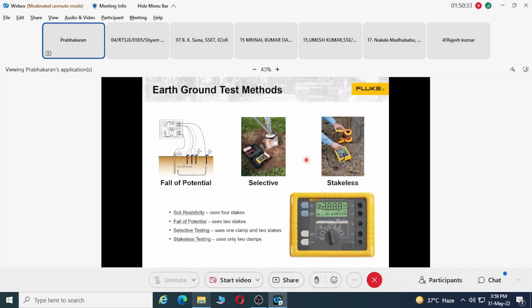Here you are using 4 stakes, and fall of potential again uses 2 stakes. You can do the same thing with two stakes also. Selective testing uses one clamp, and then there's the stakeless method, where the instrument comes with 2 clamps, 4 stakes, and 2 reels of cable to connect everything.